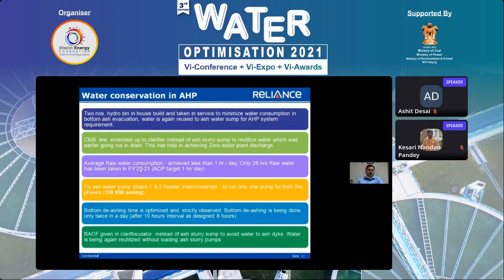Average raw water consumption is less than 1 hour per day, sir. We are managing the ash handling system in-house by continual recirculation of our system, by maintaining our ash water ratio, and it is frequently monitored. We maintain the ash water ratio strictly so that we can optimize our water. You can see our fly ash water wet system.